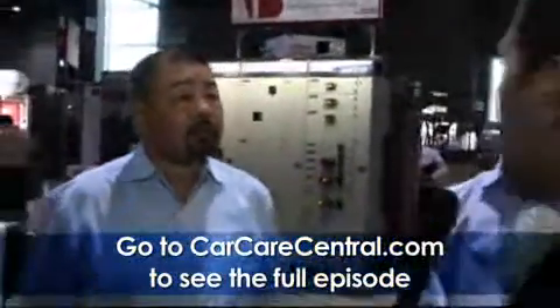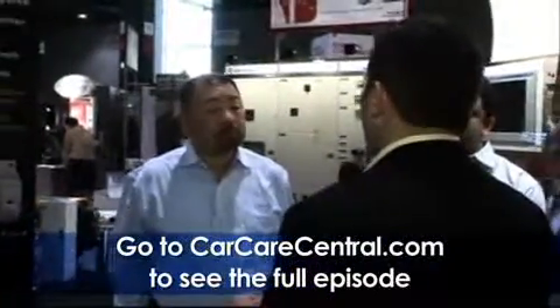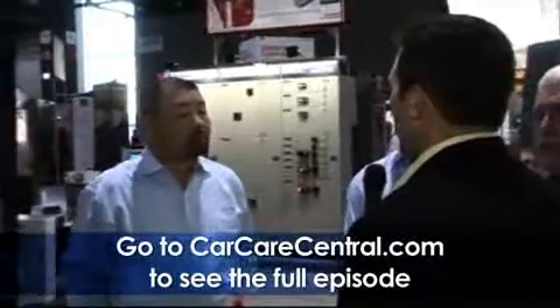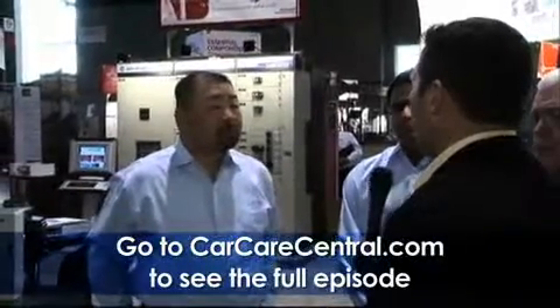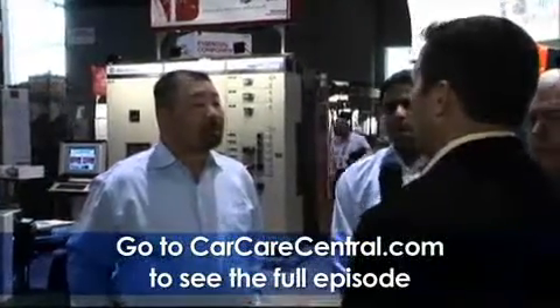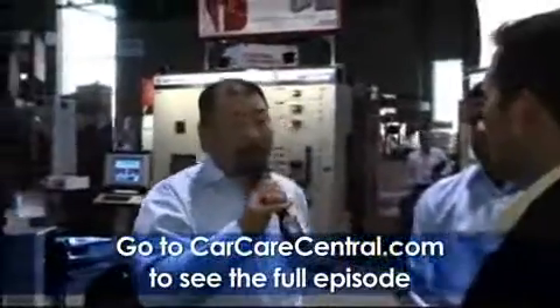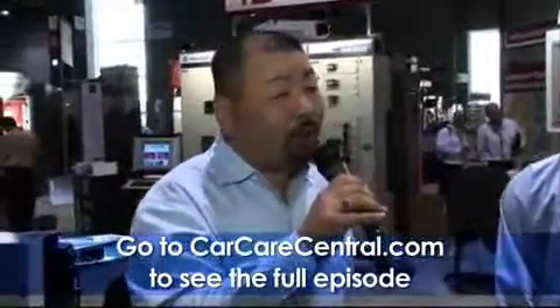So in layman's terms, we're talking about being charged all day long for a small peak period, which happens when I'm starting heavy horsepower motors like dryer fans or pump motors or something like that. Absolutely. That period of time can be measured in oftentimes 30 or 15-minute intervals. But again, you're being charged as the owner of the car wash the entire time that you're in operation.